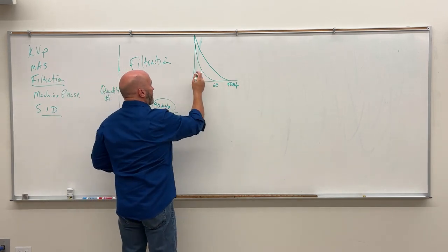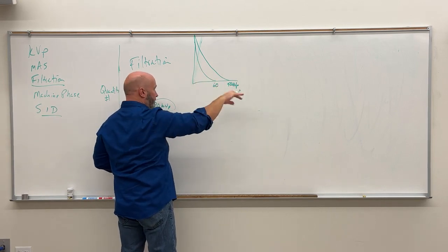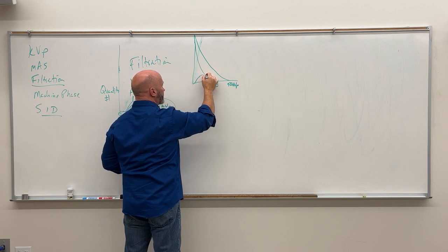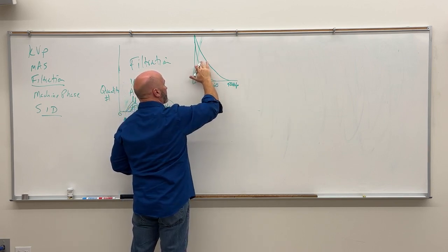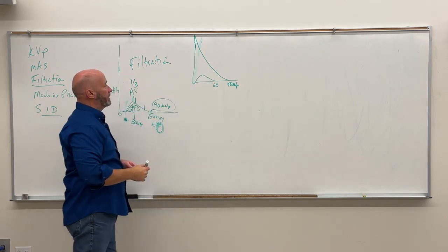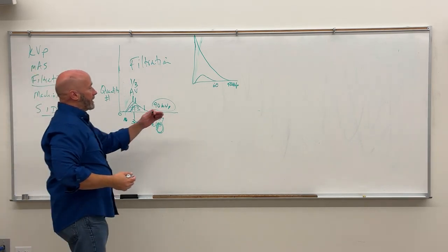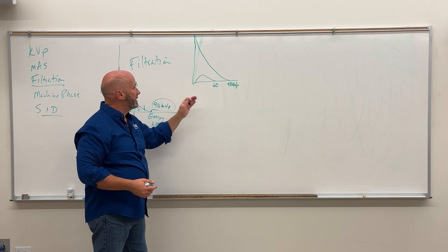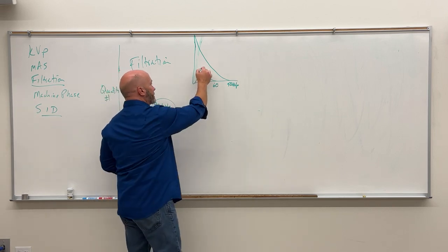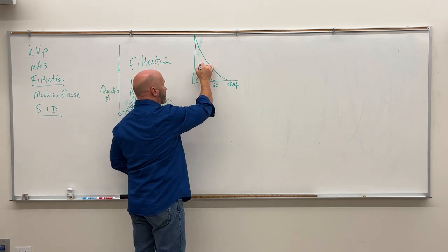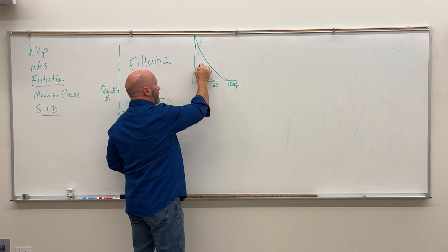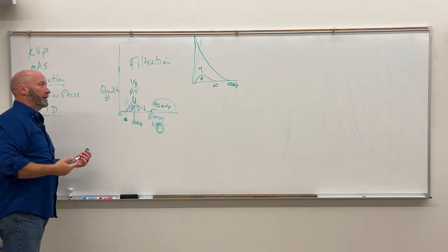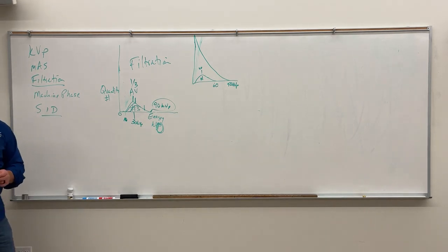So once it goes through all those levels of filtration that we talked about before, our bremsstrahlung spectrum is going to look like that at 60 KVP, right? So we've still got a lot of low energy photons. Our peak energy is 60. Our average energy is around 1/3, so our average is going to be about 20. And our numbers created are what they are, right?